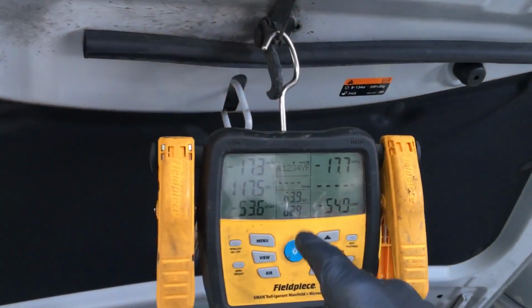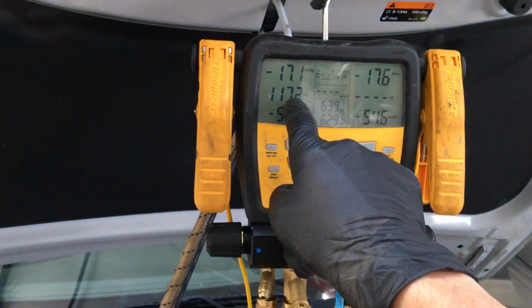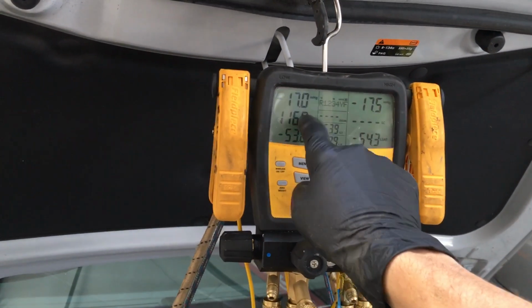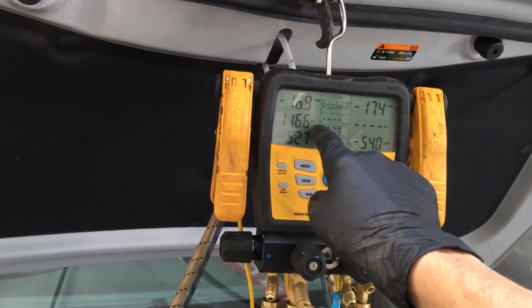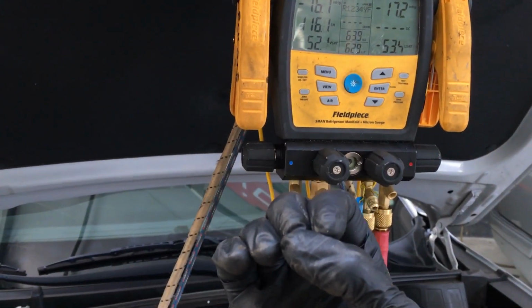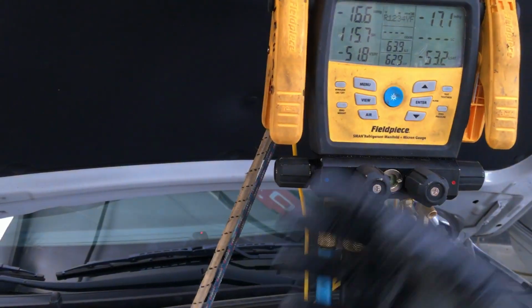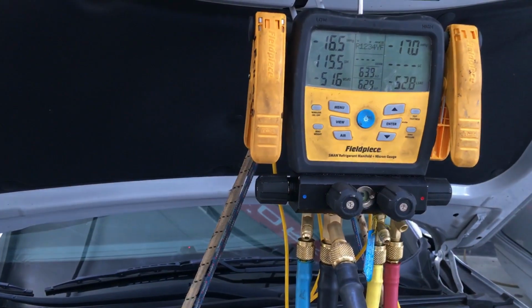And remember we were in the microns? The refrigerant is slowly boiling back out, just like carbonation inside a Coca-Cola. When you release all the pressure and put the cap back on, the CO2 bubbles out of the water and repressurizes your Coca-Cola bottle - same thing is happening here.